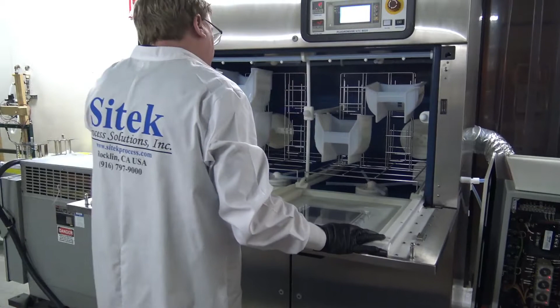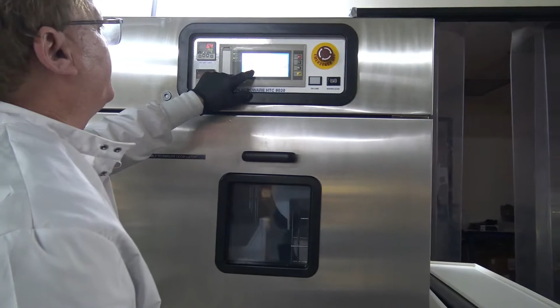Normal cycle, there we go, you heard a lock. So what happens now is that bottom DI tank starts filling up. Again, as I said, once it hits the sensor, it'll start. There's a countdown timer, see, you can see it's at 107, 106. If it doesn't fill in time, it'll abort, meaning there's something wrong with the DI water coming in.